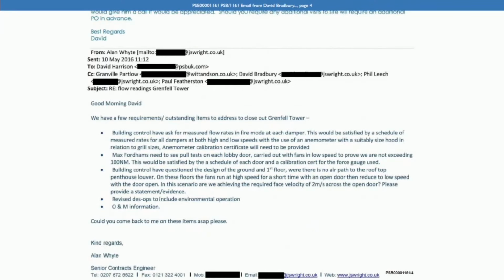So we can see that this is an email from Alan White, the second one down, from Alan White of JS Wright to David Harrison of PSB, copying in you, 10th of May 2016. And he says, "Good morning, David. We have a few requirements, outstanding items to address to close out Grenfell Tower." And you can see that the second bullet point is Max Fordham's need to see pull tests on each lobby door carried out with fans in low speed to prove we're not exceeding the 100 newtons. This would be satisfied by a schedule of each door and a calibration certificate for the force gauge used.